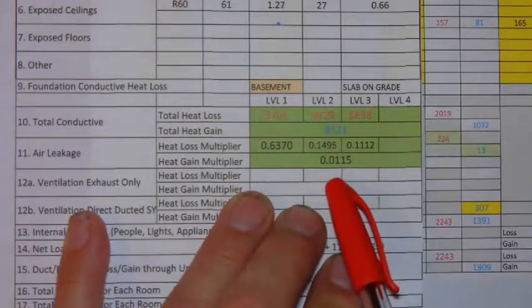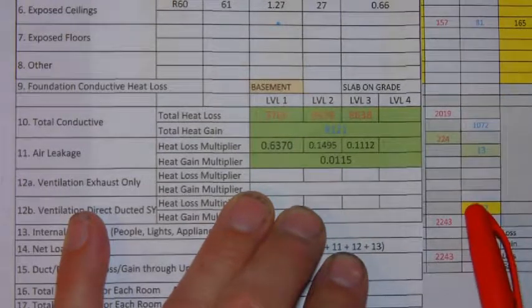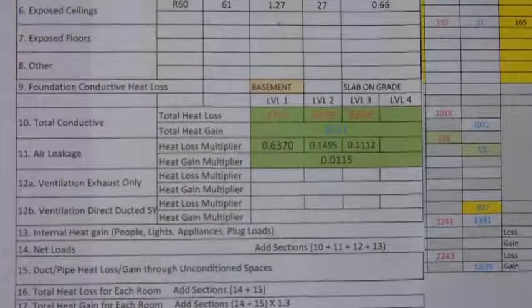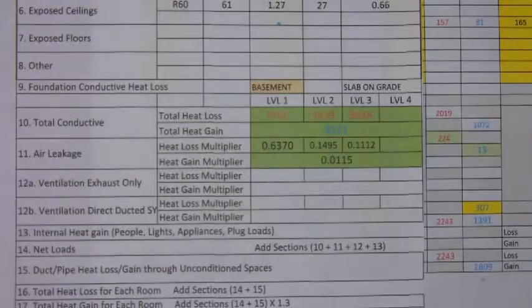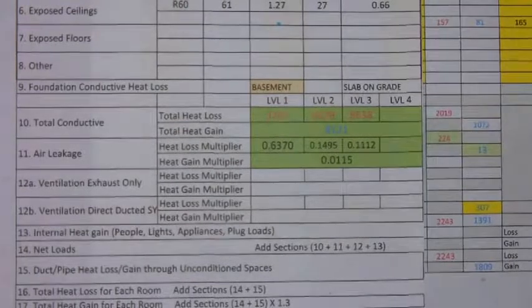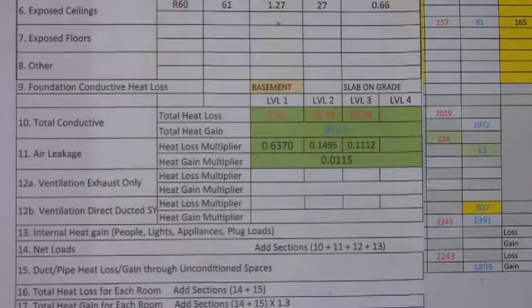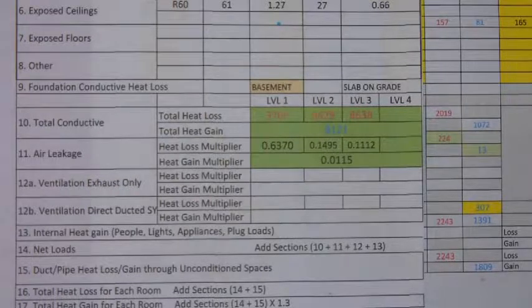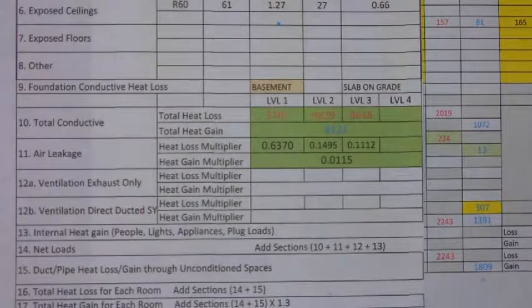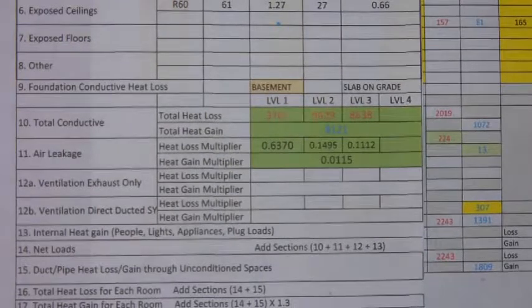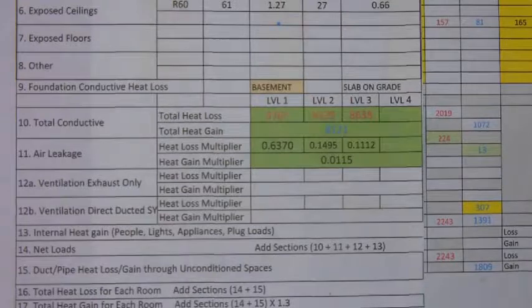And the heat gain, 1072 times the multiplier of 0.0115 would give us a heat gain of 13. You would carry this process through for all the different rooms on each level. Just make sure that you multiply the heat loss of a level two room by the level two multiplier and the heat loss of a level three room by the level three multiplier.